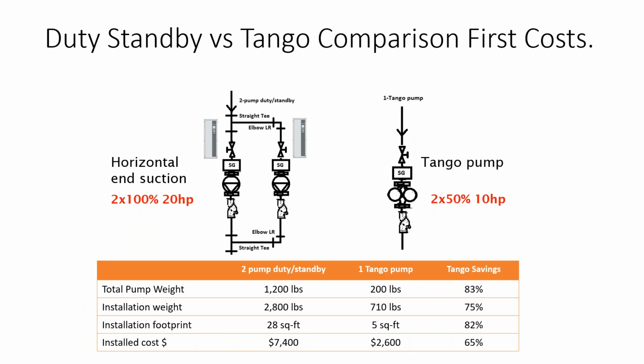Here's a little study, duty versus standby comparison, your first cost. Based on horizontal end suction pumps, you'll have 2 by 100% with 20 horsepower motors, and the Tango is once again the 2 at 50%, which is 10 horsepower. The total pump weight right off the bat is 1,200 pounds for the horizontal end suctions. The Tango is 200. That's a tremendous 83% savings in weight. The installation weight, which is the concrete pads and all the extra piping necessary to have individual pumps, is 2,800 pounds. The Tango with the single hookup, 710. Once again, huge savings. The footprint, though, this is shocking: 28 square feet versus 5 square feet.